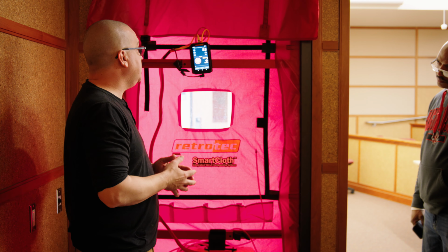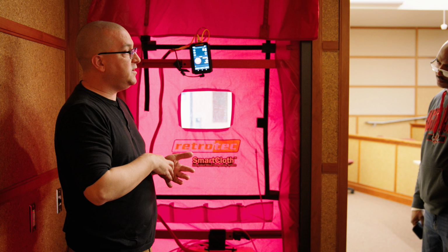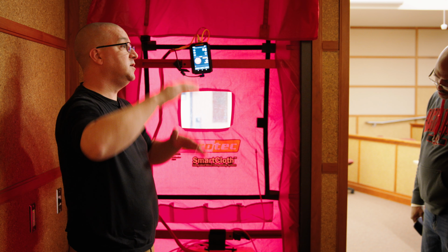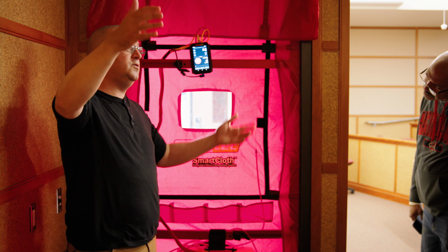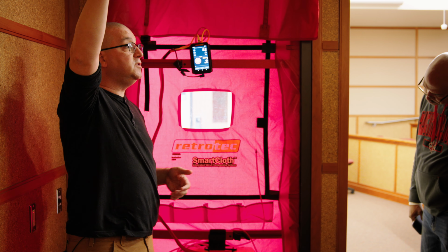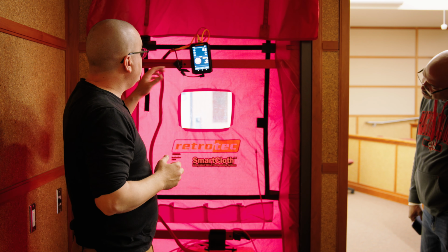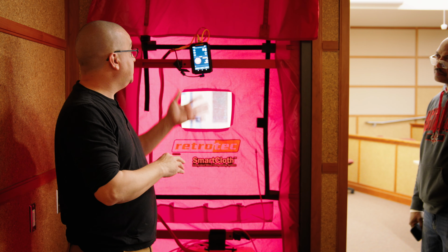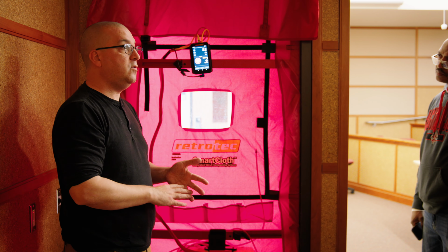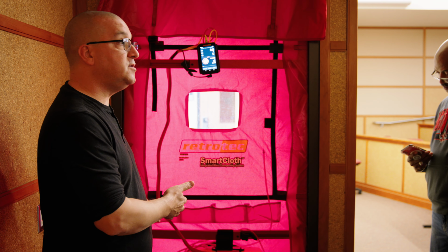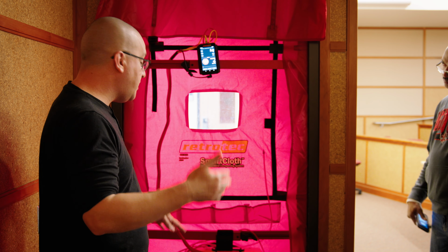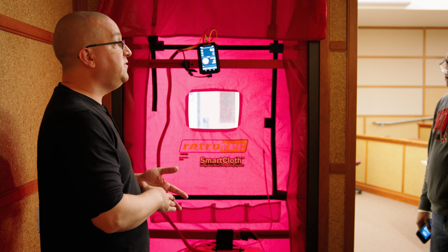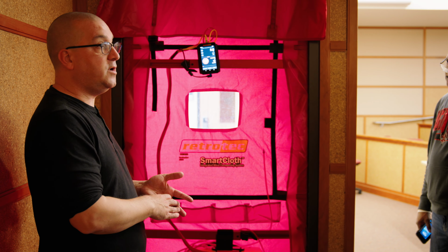With this manometer, you can input all of the information about the building: the square footage, the volume of the space, and the surface area, so the walls, the ceilings, the floors. If you input all that information, it can automatically tell you what the air changes per hour is. Normally we're depressurizing, so we're pulling the air out of the house. That's how I typically run a blower door test, and certainly for new construction, that's how I'm going to run it.